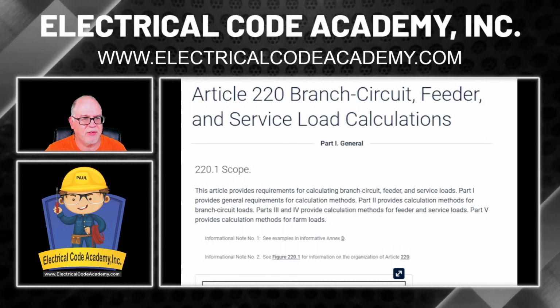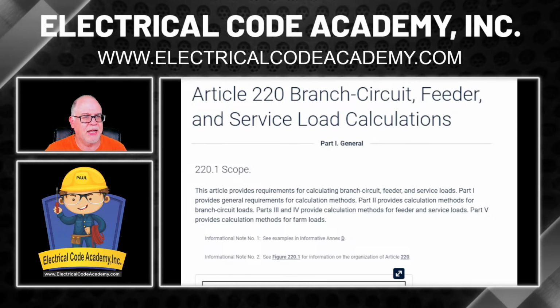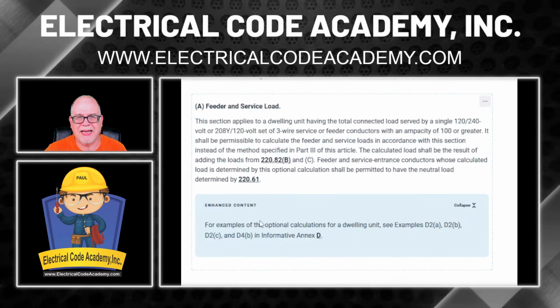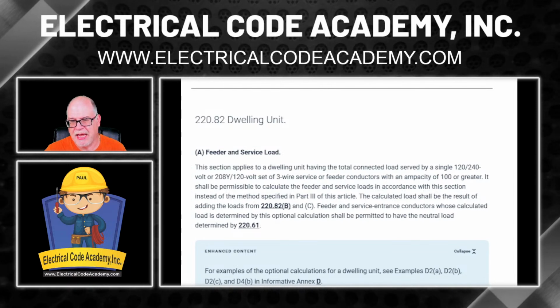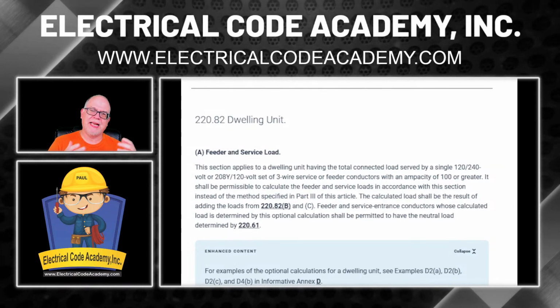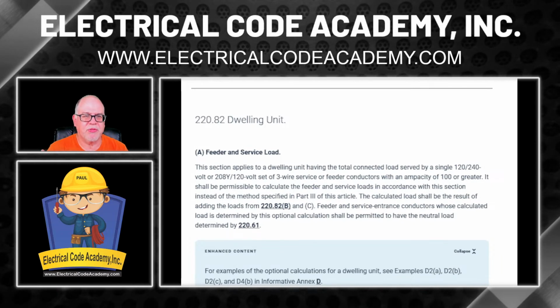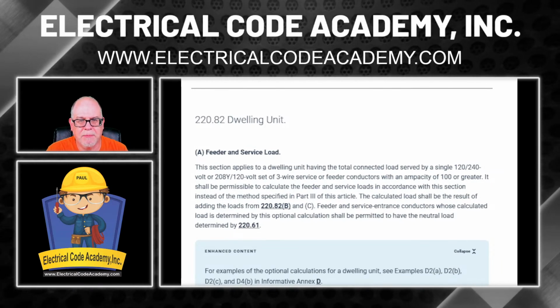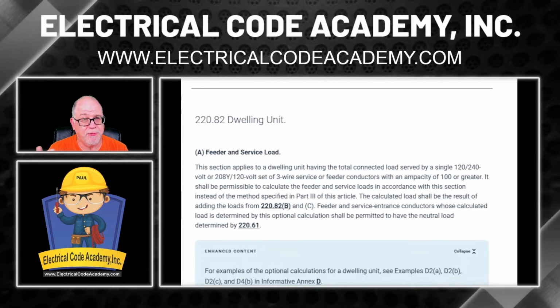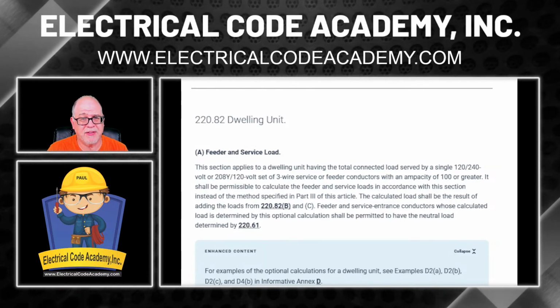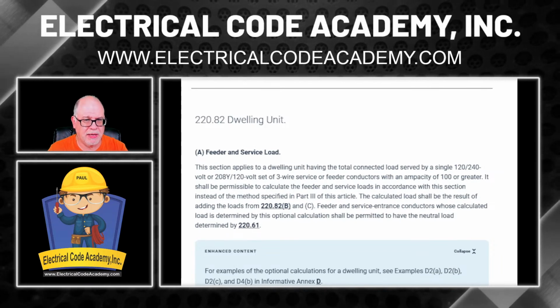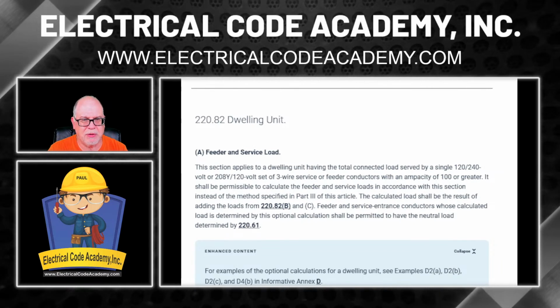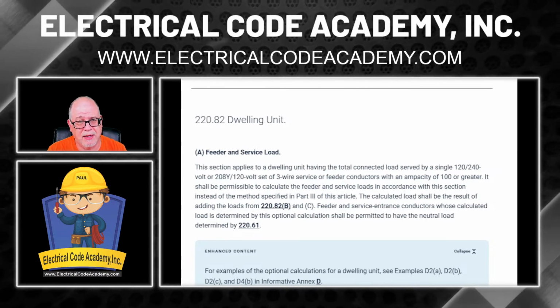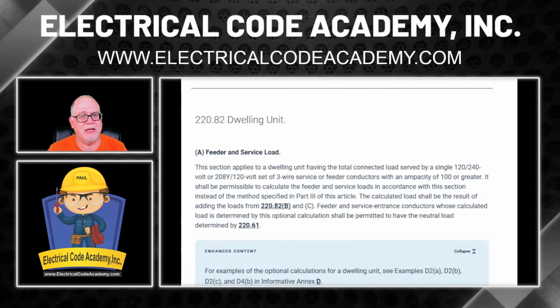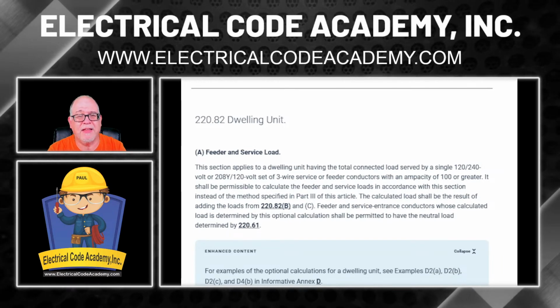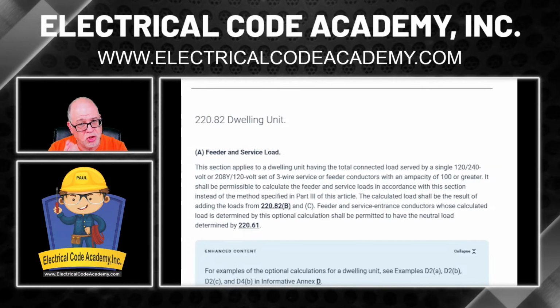And I'm going to take us down to where we need to be. And as you know, we're in 220.82. Now you might be asking, why are we in 220.82? Well, we are doing the optional method. So that's part 4. We wouldn't be in 220.84, in case anybody asks, because that's dealing with multifamily dwellings, and we're not dealing with a multifamily dwelling. We're dealing with a single family dwelling, so we're not dealing with 3 or more. We're dealing with 1. So that's why we're in here, and that's why this is titled Dwelling Unit.